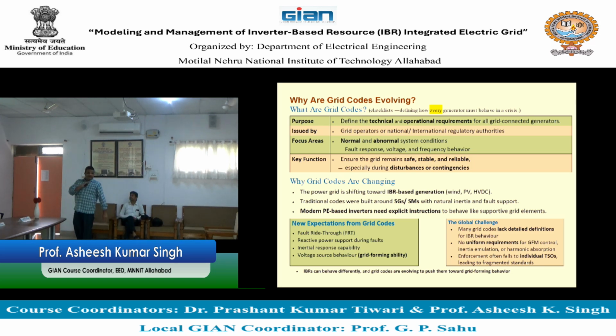What is the fault ride through capability? Reactive power support during faults means abnormal operation situations, inertial response capability, and voltage source behavior or grid forming ability. So these are the new expectations.